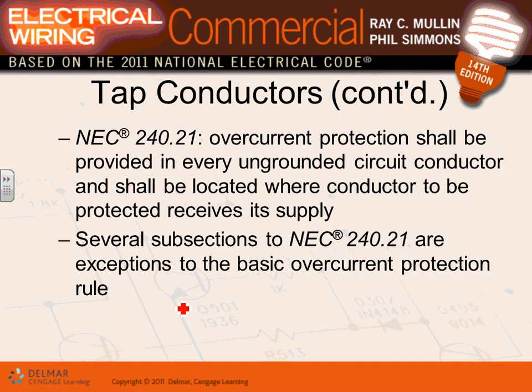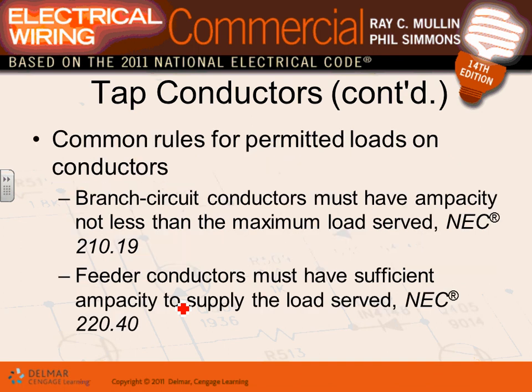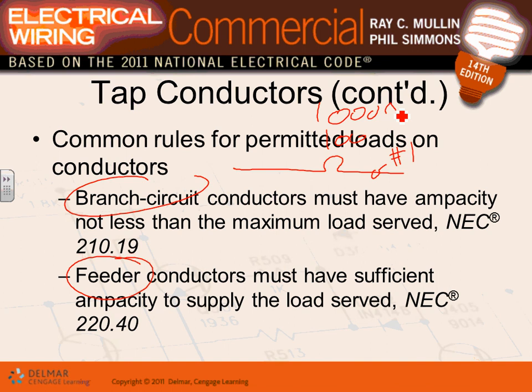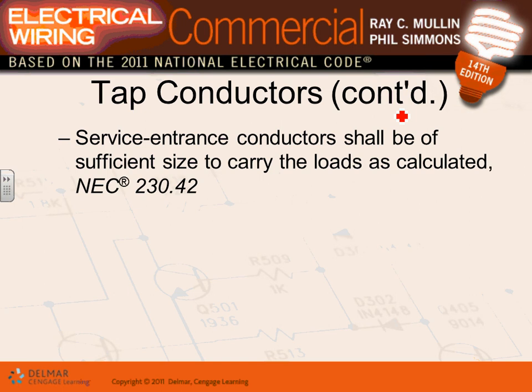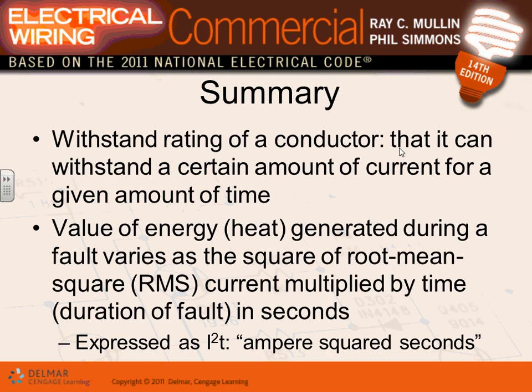Overcurrent protection shall be provided in every ungrounded conductor. There are several exceptions for this one, for the tap. And this is just telling you the things that you know for feeders and branch circuits. If you have a 100 amp panel, you put your number 1 here, right? You cannot put 1,000 amp here, can you, on a number 1? That's what you have done with me for branch circuits and feeders. The tap is an exception to this one. Service entrance conductors also have to be rated to carry the calculated load. You have just done the calculation with me to do that. So that's basically it, guys, in terms of the calculation.